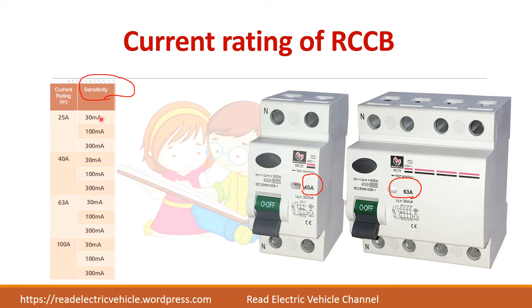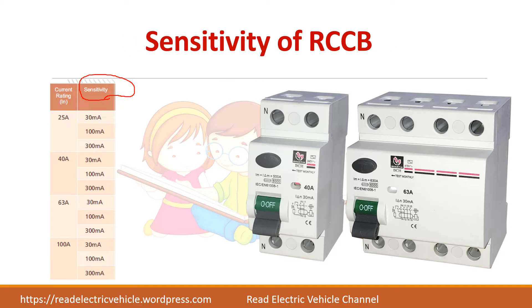For example, for a 40 amp current carrying capacity, the sensitivity is given as 30 milliamps. Sensitivity can be 30 milliamps, 100 milliamps, or 300 milliamps. The 30 milliamps refers to the sensitivity of the RCCB — it indicates the residual current level at which the breaker will trip.